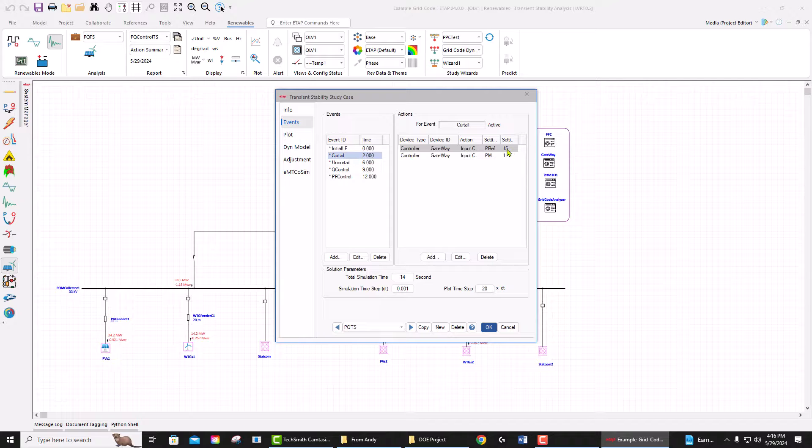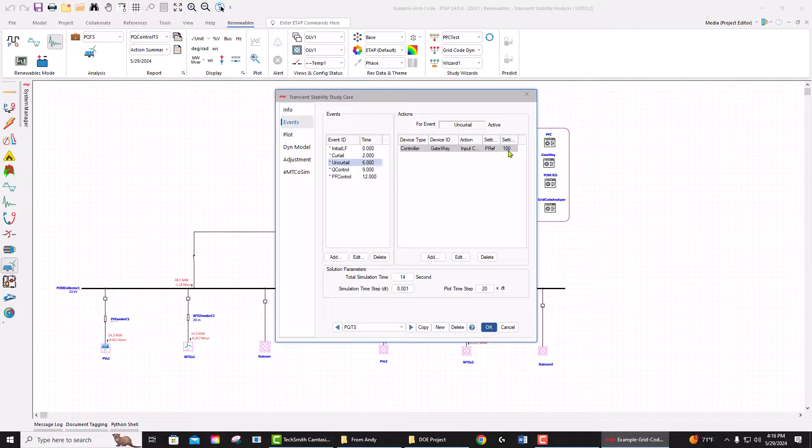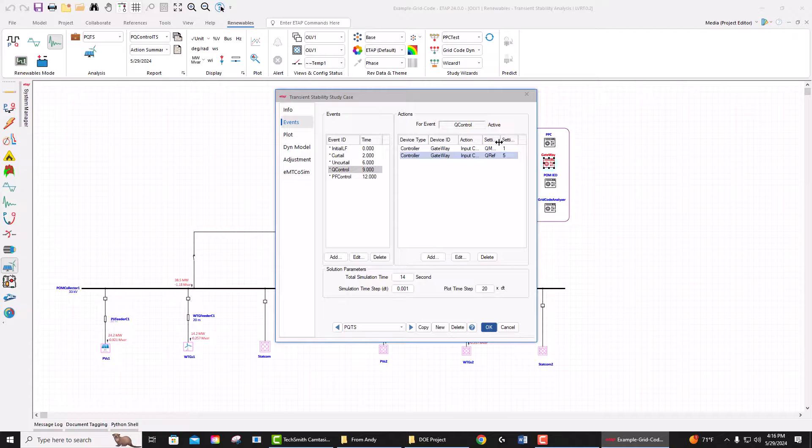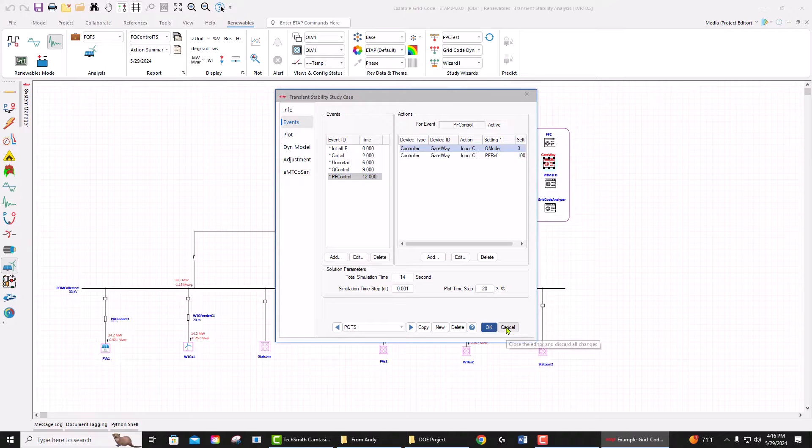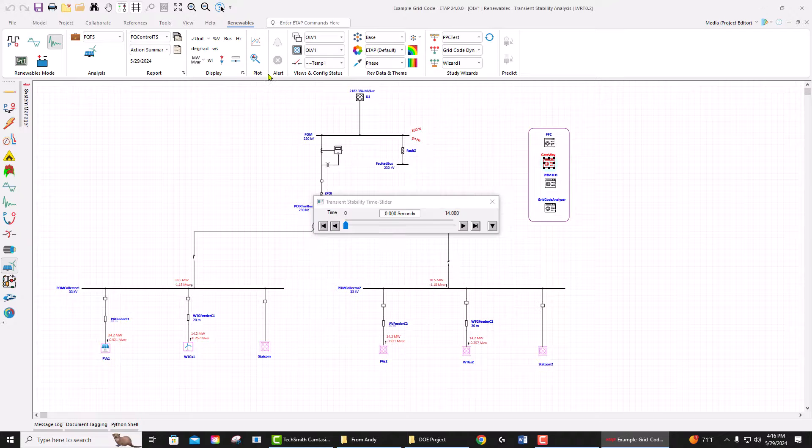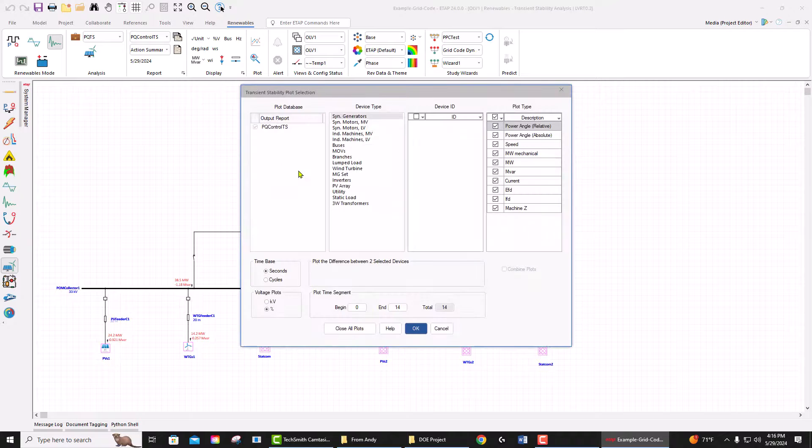curtail the power to 15 megawatts, and then we send the command at six seconds to uncurtail. We send the command at nine seconds to change the reactive power to the Q control and to five megavars. At 12 seconds, we change the reactive power control to power factor control at 100 percent power factor. Now let's look at the response of the system.